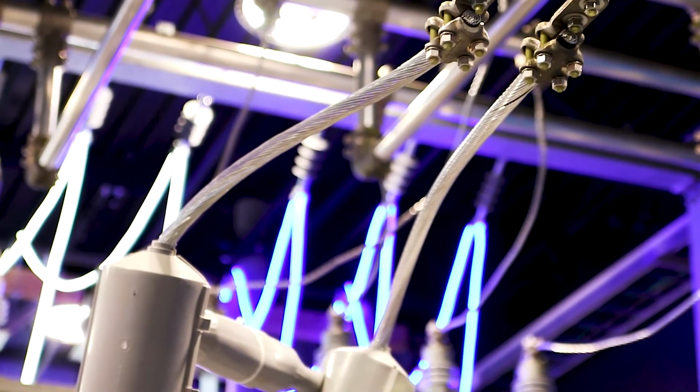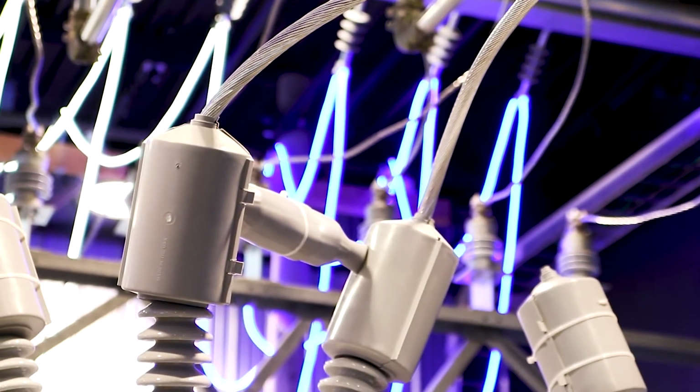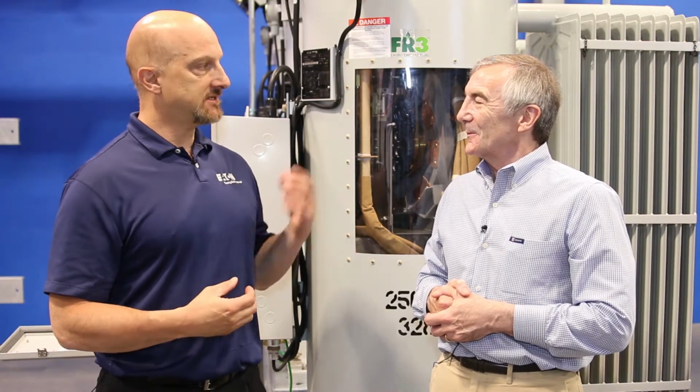So what do you do? Well, it's more around control, and actually changing the way the regulation is done, and maybe sizing the capacitor banks a little bit differently. And for large solar installations, sometimes they use those instead of the capacitor banks to regulate the reactive power flow. So it's really a coordination of efforts. It's not just allowing it to happen, it's actually coordinating all those efforts, working with the control, and making sure the equipment's sized correctly.